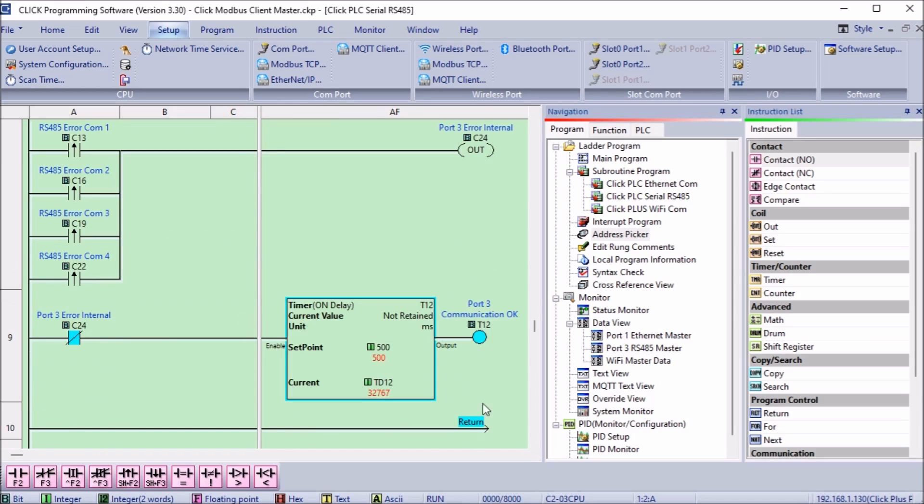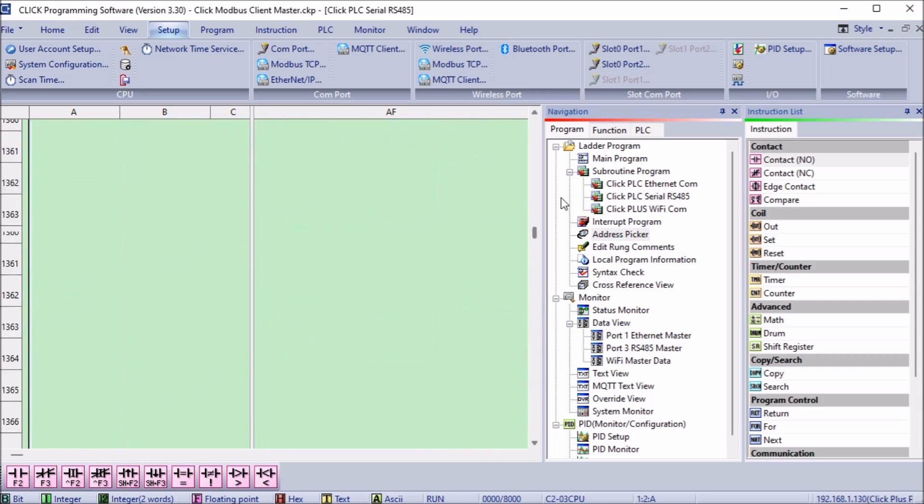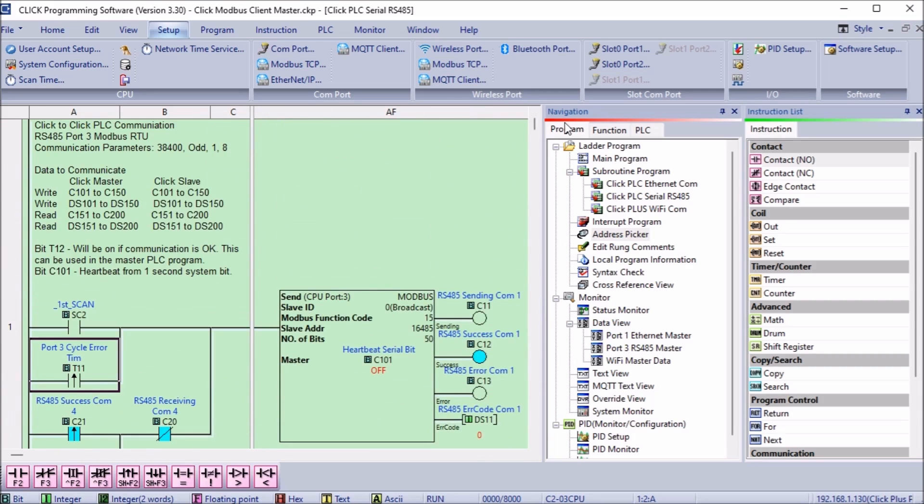The normally closed of this bit will then turn on a timer. The timer is set for 500 milliseconds or one half a second and if the timer done bit is on then communications are okay. We can then use this in other areas of our program.